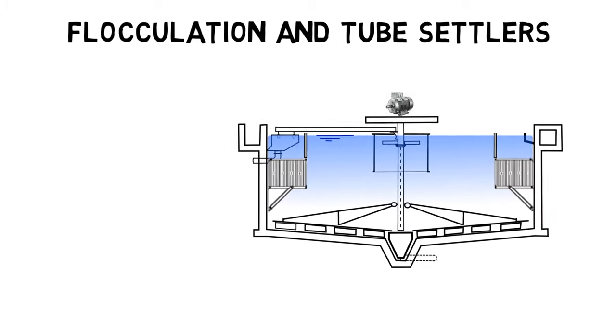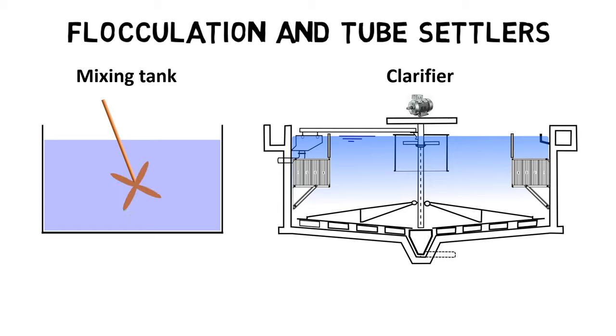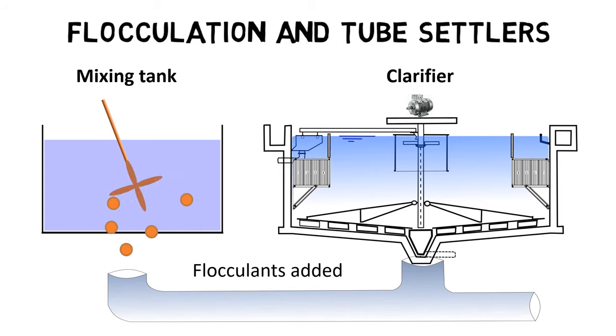In many cases, flocculants or coagulants are applied to the wastewater before it reaches the clarification tank to make the sedimentation process more effective. The chemicals are usually added in mixing tanks with agitators which provide gentle stirring for even distribution of chemicals in the water.